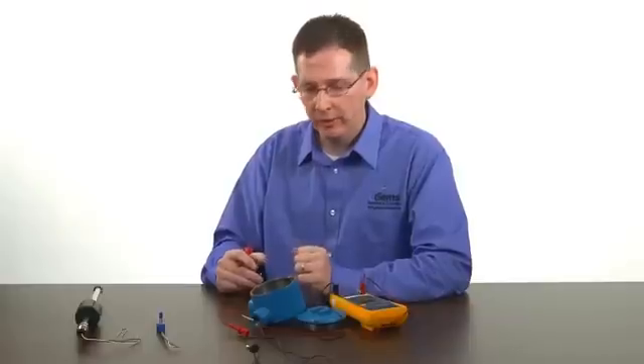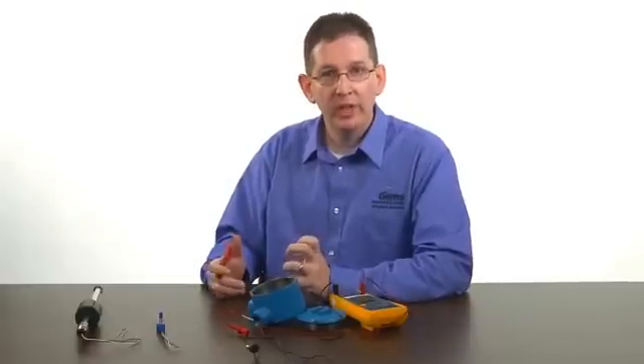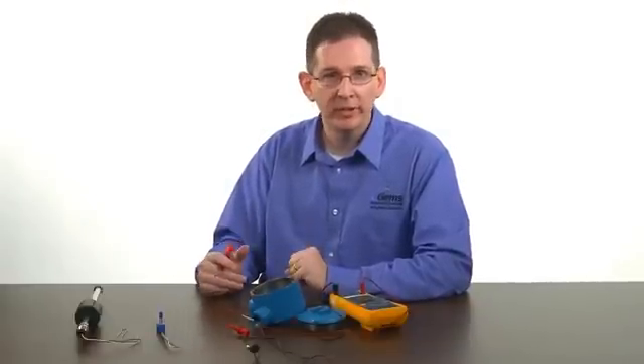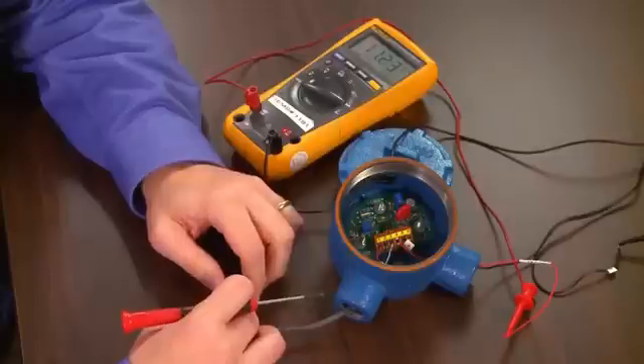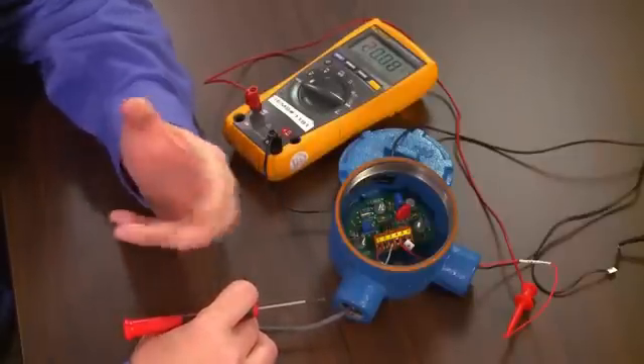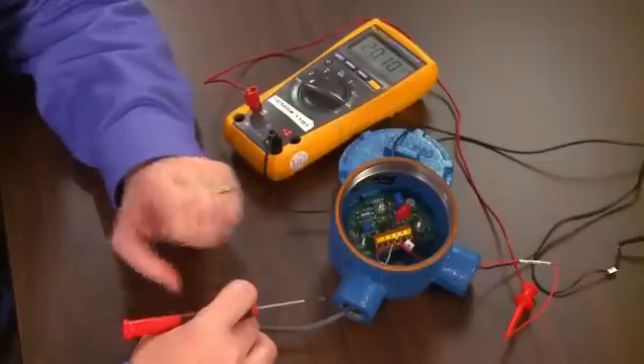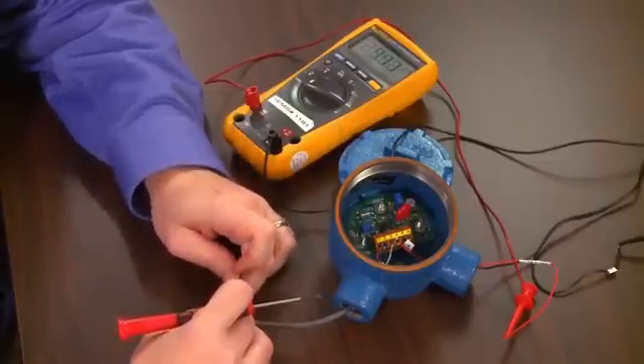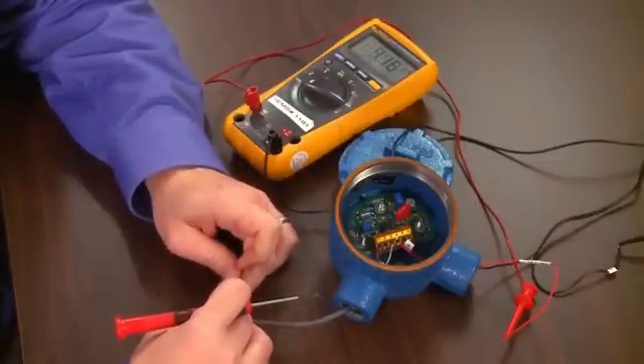Once you have your potentiometer connected we want to establish the direction of raising and lowering its output. Turning the potentiometer clockwise you'll notice on the multimeter that the output goes towards 20 milliamps. Counterclockwise the output drops towards 4 milliamps.